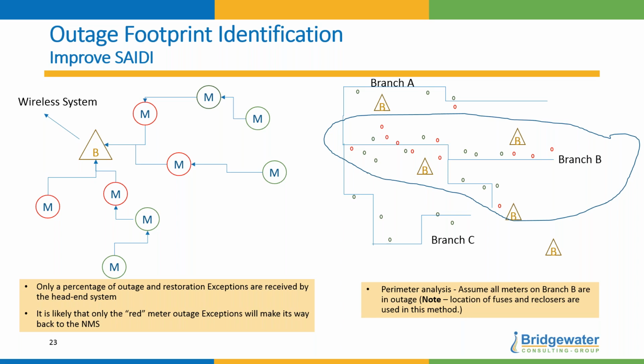what the footprint is. And the reason is that when you have the connectivity model, a lot of meters can't respond, because if a meter is sending out a notification and the meter in front of it is also out, that meter is not going to listen. But if that meter is talking to another meter that's not part of the outage, that meter can listen and pass on the notification. So by knowing the network configuration, the connectivity model, getting those initial power outage notices, and just doing simple algorithms of perimeter analysis, you can get a fairly good handle on where the fault is and what the footprint is, without having to wait for a full set of phone calls to come in.